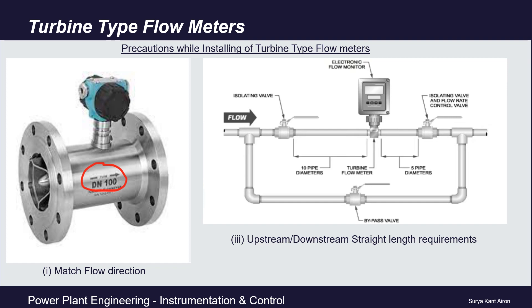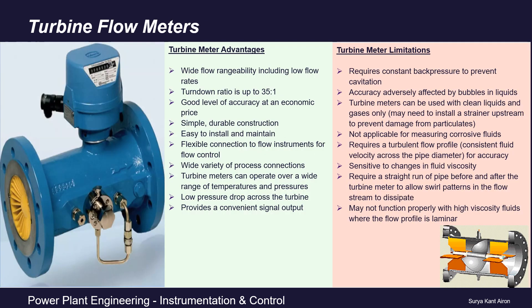Turbine type flow meters are widely used because of their wide flow range ability including low flow rates, and they have a very good turndown ratio of 35:1. Accuracy level is very good relative to their price, so at an economical price they provide very good accuracy. They have simple, durable construction and are easy to install and maintain, with flexible connection to flow instruments for flow control. They offer a wide variety of process connections and can operate in a wide range of temperatures and pressures, with low pressure drop across the turbine.